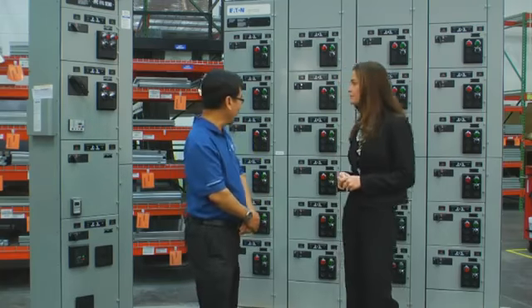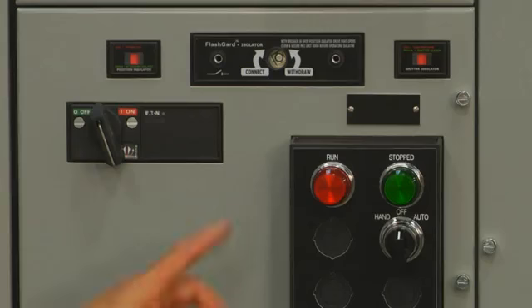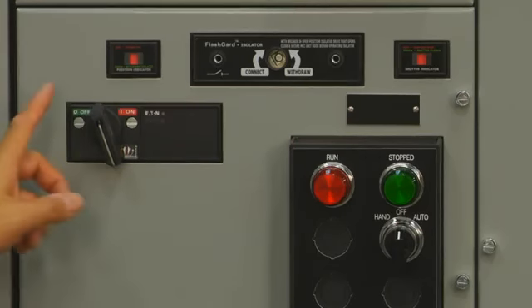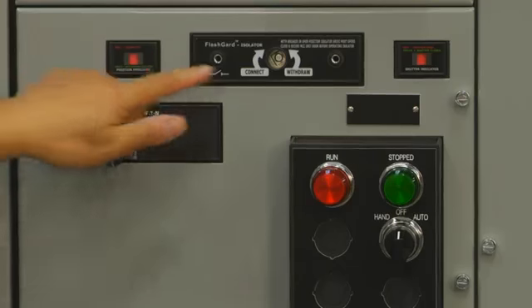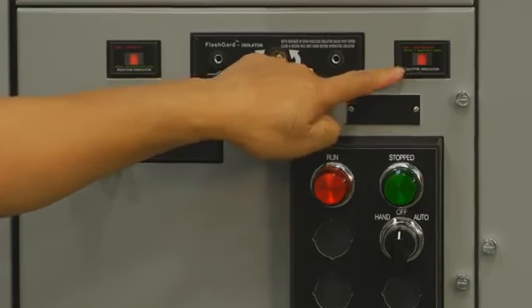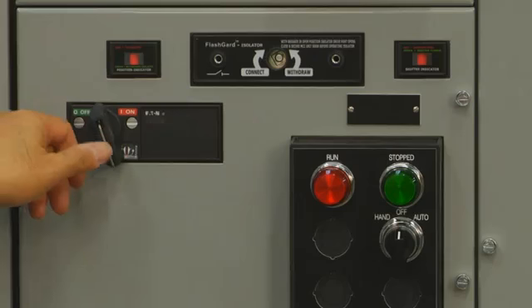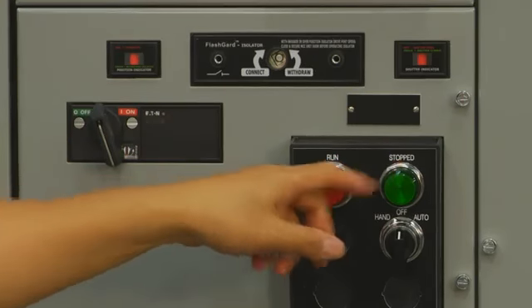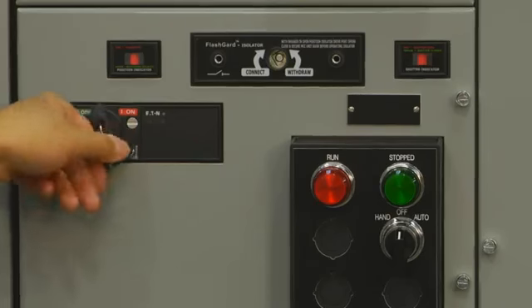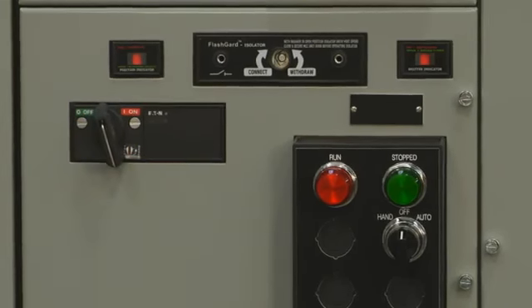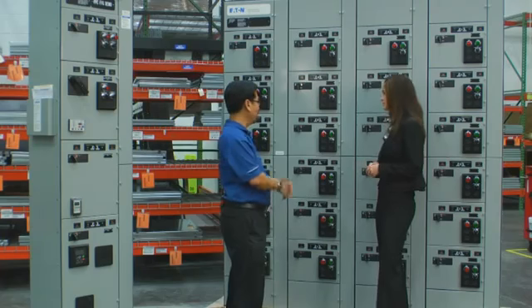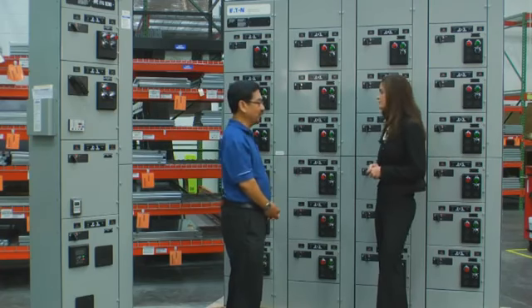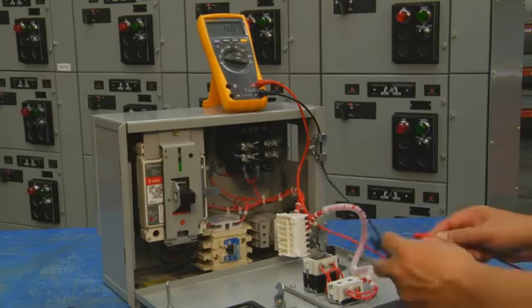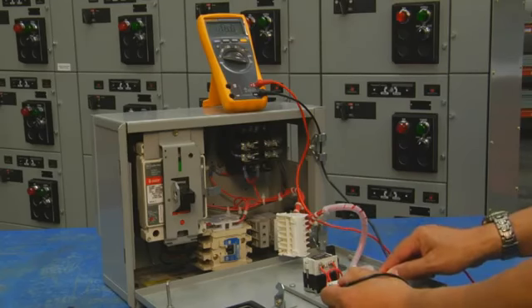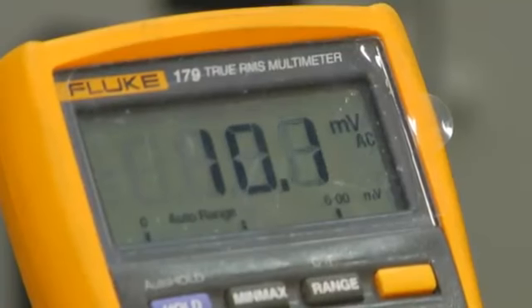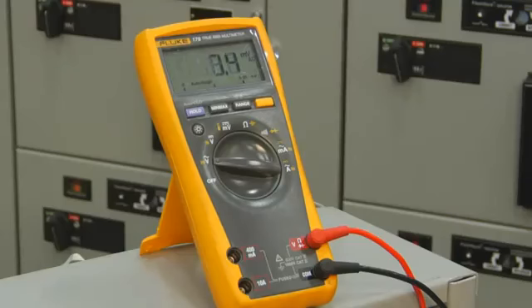In addition, we have designed the FlashGard MCC with through-the-door controls, as well as visual indicators, that allow plant personnel to operate the motor control center without ever having to open the enclosure door, as well as run and stop push buttons. But in the end, somebody is going to have to open up the enclosure door to perform routine maintenance or for troubleshooting. But with FlashGard MCC, there will never be any surprises when you go inside. For example, with conventional MCCs, the door must be open in order to use a multimeter to perform a test before touch procedure to make sure that the bucket is de-energized.